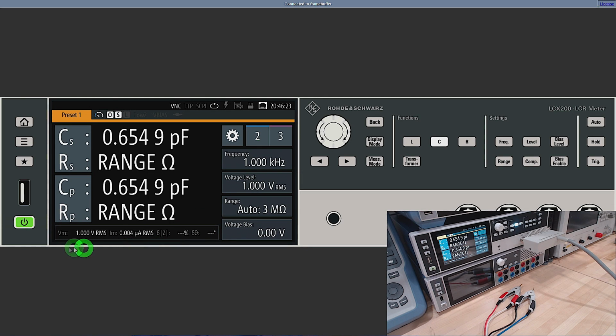Now at the bottom, the instrument measures the actual incident voltage and the measured current that's being applied to the device under test, but it also shows you two other parameters, which is the confidence in the measurement of the impedance and the phase. This too is extremely helpful, especially if you are near the borders of the accuracy of the instrument. It tells you right away whether you're in a favorable spot or not, or how much confidence you can have in your measurement, and this is a complex calculation that is done internally.